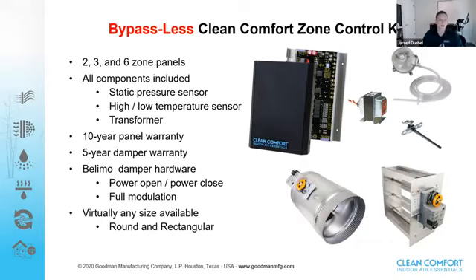Okay, so first of all, on the bypass-free zone control system and on the standard zone control system, we have three different panel options. We're going to have the two-zone panel, which is just the more rudimentary single-stage panel. Then we're going to have two different versions of the three-zone panel. We have both multi-stage versions. One's going to be a heat-cool multi-stage for a conventional setup, and the other one's going to be the heat pump or dual fuel series. And then the third version of the panel that we have is the 6-zone zone control panel. Now you can add an expansion panel, which adds 3 additional zones to the 6-zone panel. You can add up to 2 of those, which means that we can offer a zone control system with the Clean Comfort line anywhere from 2 to 12 zones.